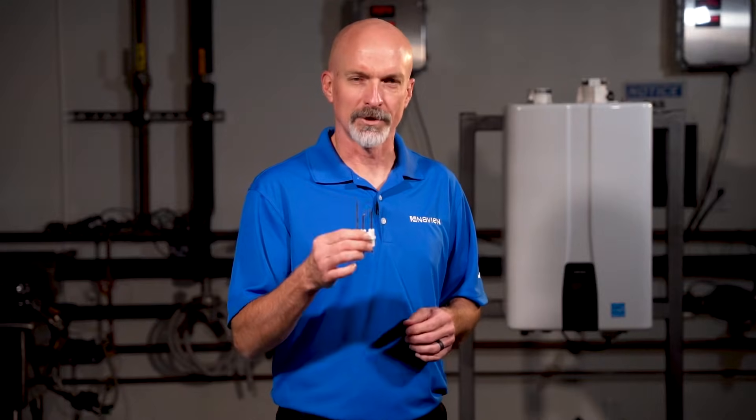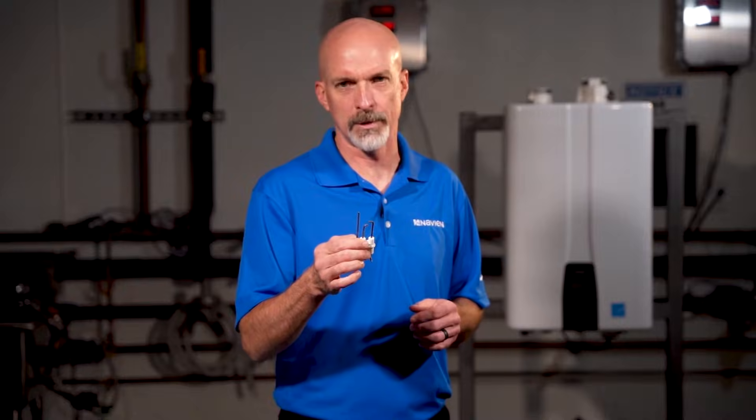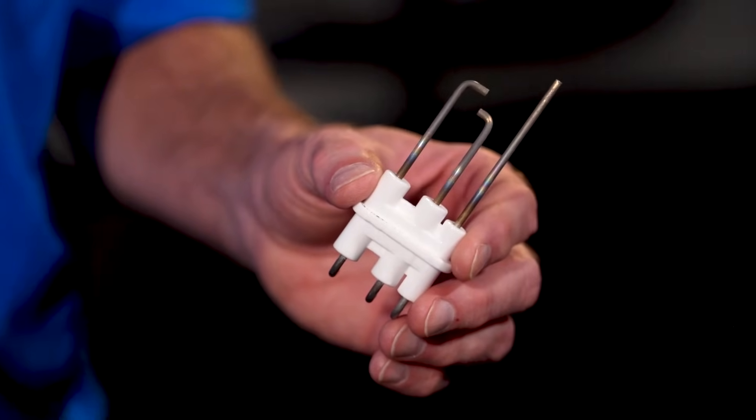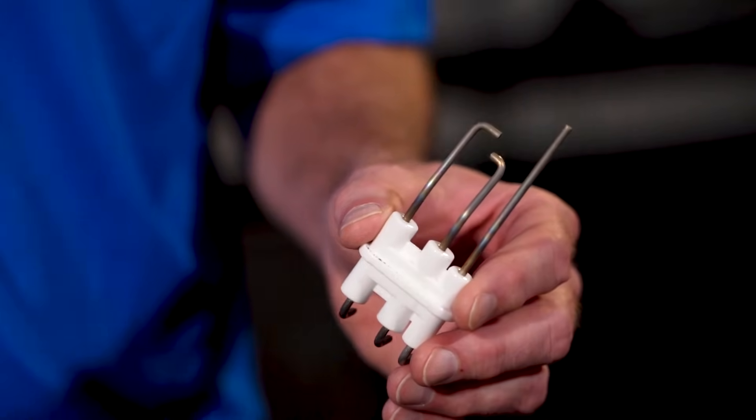The flame sensor is another component we rely on to keep the unit safe. The flame sensor inserts into the burner chamber; it monitors when the burner lights and stays continuously lit, and if the flame would drop out for some reason, it will shut the gas valve down, stopping any operation of the unit.